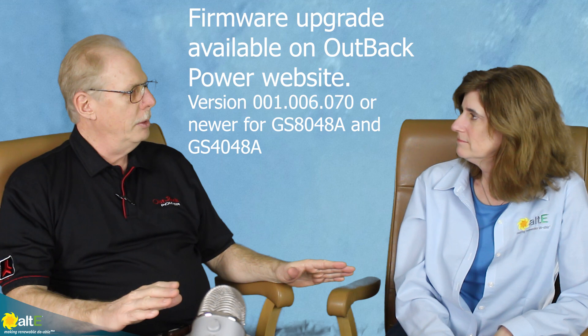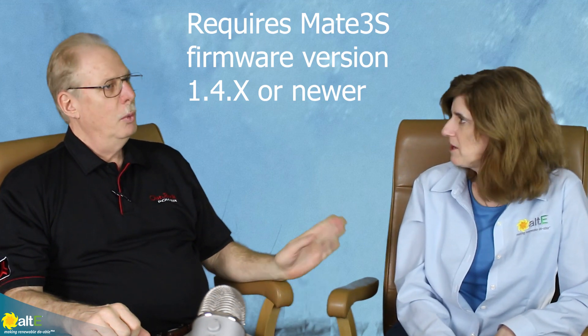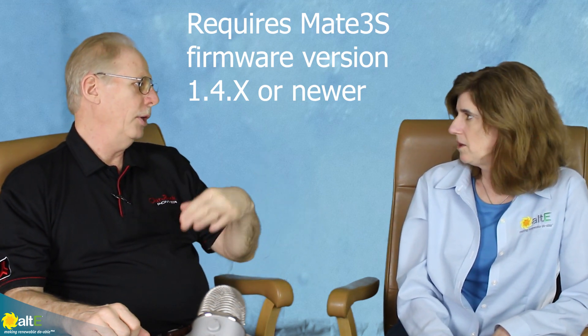Is this solution software upgradable? Glad you asked — yes, it is just a software upgrade. You will never order an AC coupling firmware version from the factory. It uses a standard Radian — our GS8048A-01 or the GS4048A 4000-watt version dash-01 — and it does require a MATE3s with the latest firmware version 1.4.x or newer. The inverter firmware needs to be downloaded from our website, so this will never ship with it pre-installed. There's no additional cost — just a set of batteries and a Radian inverter and you're good to go.